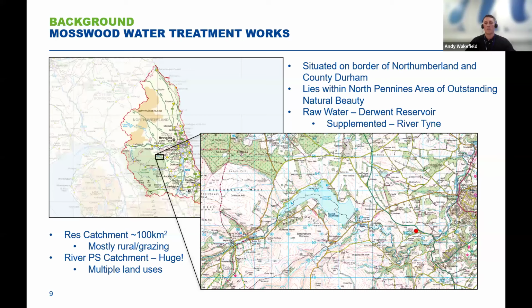The works can also be fully supplemented with an alternative raw water supply, which is from the River Tyne, and this is through a pumped arrangement, which is part of our Kielder transfer system. The Kielder transfer system allows us to move water from the much larger Kielder Reservoir up in Northumberland around much of the northeast. It's particularly vital for maintaining flows to the Tyne, the Wear, and the Tees rivers. And we also have the availability to supplement some of our water treatment works with that source. The reservoir catchment for the Derwent is mostly rural and sheep grazing. It's approximately 100 kilometres squared, but the river pumping station catchment is significantly larger with multiple land uses throughout.